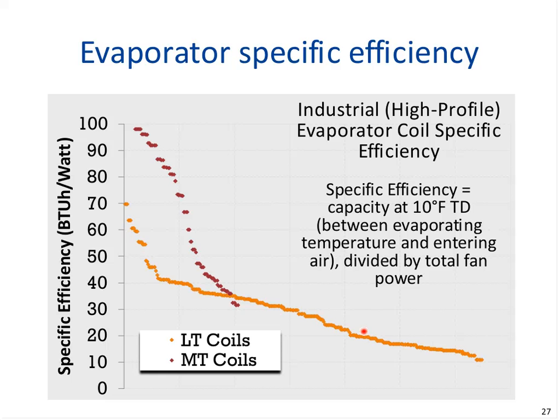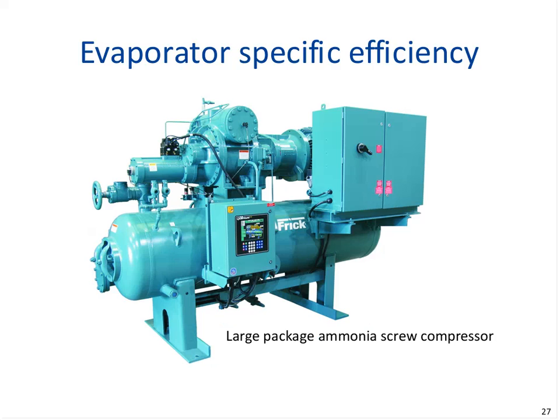As a general rule, anything above 30 to 40 would be considered efficient evaporators, and all these down here would be less efficient. This is a function of tube and fin spacing, motor efficiency, and I think there's about 400 or so evaporators depicted here for both medium and low temperature. And of course, medium temp here and low temp, these would be considered not so efficient. So do your homework when you actually consider your evaporators.